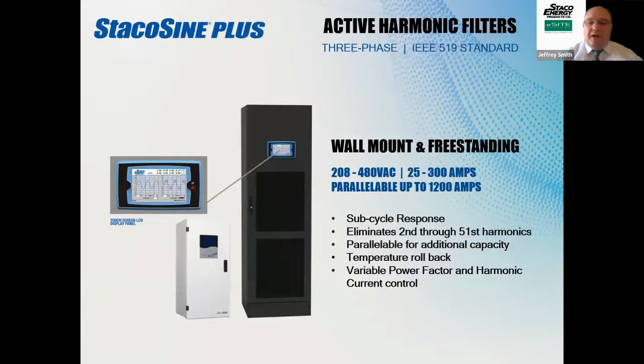This is what our harmonic filter looks like. We have wall mounted and freestanding versions. Typically it's going to be a freestanding type system. They can go from 25 amps all the way up to 1200 amps, and what we do is we parallel the systems up to what we need.